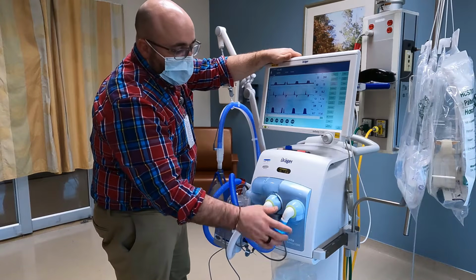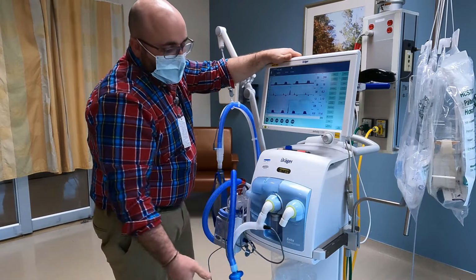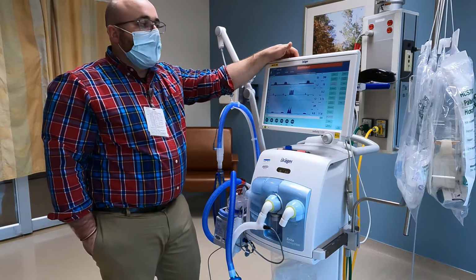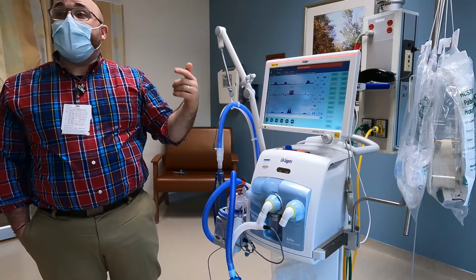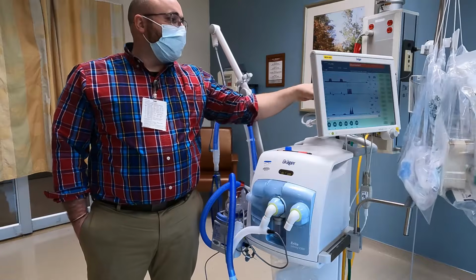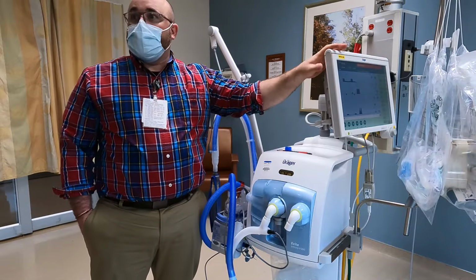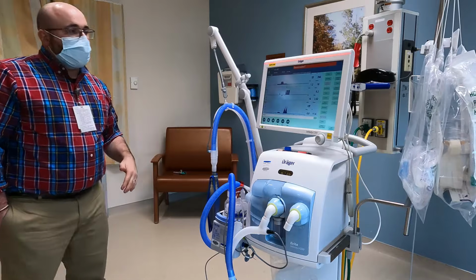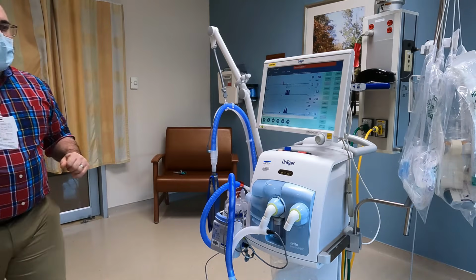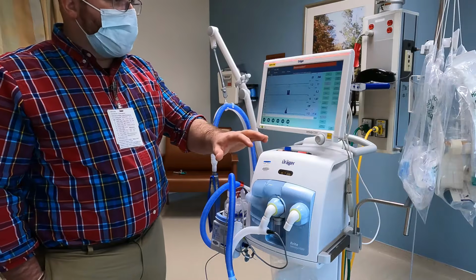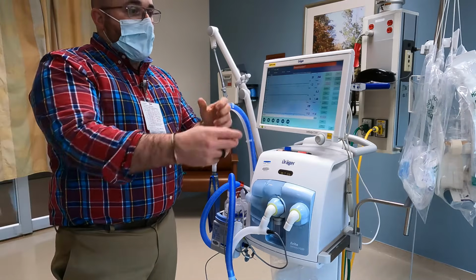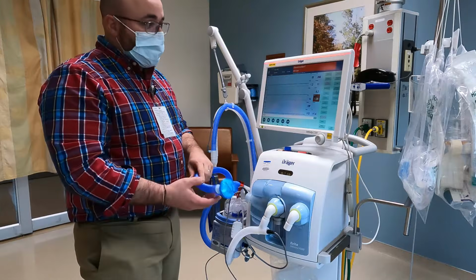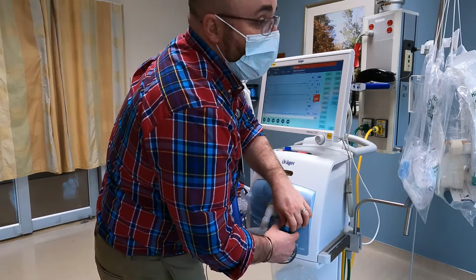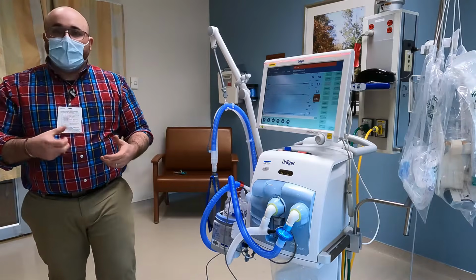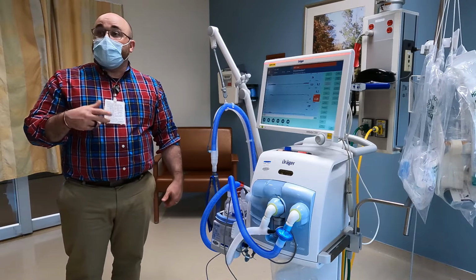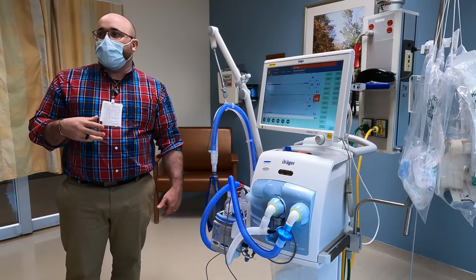So let's do a red alarm. So if something pops off, red alarm, disconnect. It escalates in sound. Even if this faces away, you can still see the red on it, okay? So you come into the room on this patient, first thing you're gonna do is check on the patient, okay? Is there a problem with the patient? No, there's not a problem with the patient. You could even, if you're not for sure, see how it gets louder? If you're not for sure, take them off, attach them to a bag valve mask, ventilate them, call RT. It's better to do that than to try to troubleshoot this and fix it.